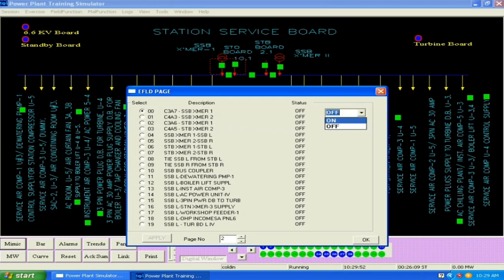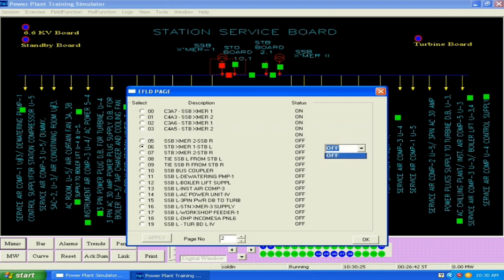So on page number 2, index number 00 to 03, these are the 6.6 kV transformer primary side. So the station service board transformer 6.6 kV is up to 03, and 04 is the 440 volt breaker. So the breaker on the secondary side of the SSB transformer is also to be made on. So 4 and 6, you can make them on.